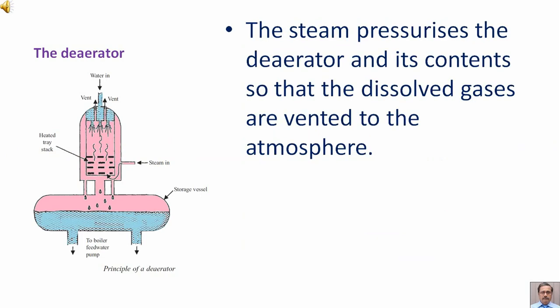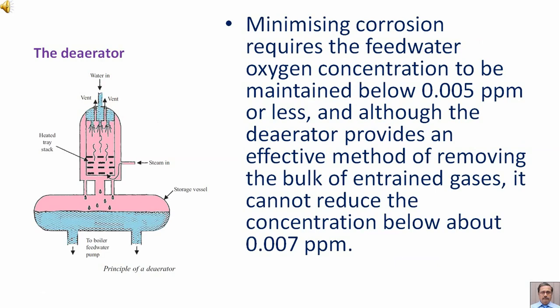The steam pressurizes the deaerator and its contents so that dissolved gases are vented to the atmosphere. Minimizing corrosion requires the feed water oxygen concentration to be maintained below 0.005 parts per million or less. Although the deaerator provides an effective method of removing the bulk of entrained gases, it cannot reduce the concentration below about 0.007 parts per million.